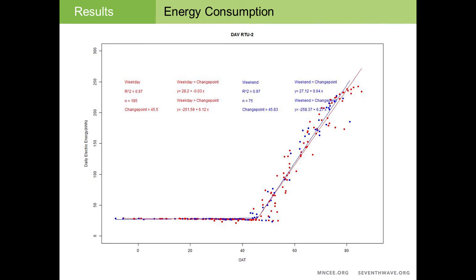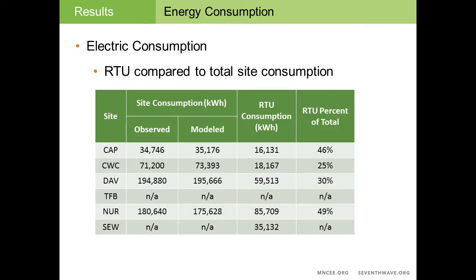And here's our site that I mentioned before, which is the restaurant site. There's no difference in weekday, weekend, which probably you would expect for a restaurant type facility, but what's interesting here is that the change point for this model is at 45 degrees. So mechanical cooling is being initiated above 45 degrees, which for me tells me the economizers are not working properly for this particular unit.